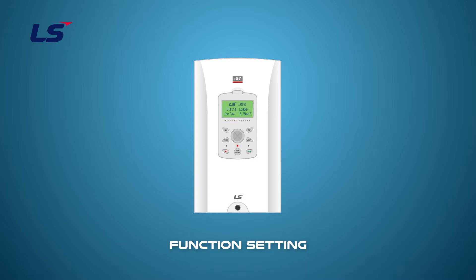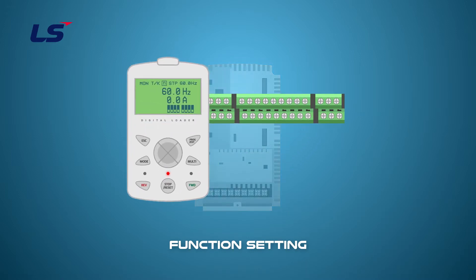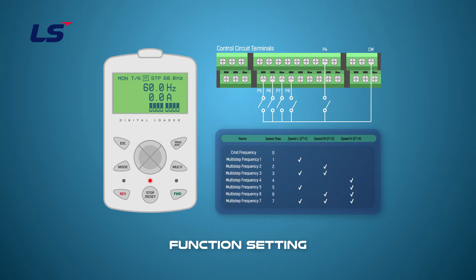The settings for multi-function terminals Speed-L, M, and H operate by binary sequences. The following table shows the input sequence for each single digit. You can also check it on the keypad display. When terminal P5 for multi-step frequency, which is Speed-L, is ON, it is step frequency 1. When terminal P6, which is Speed-M, is ON, this is step frequency 2. The control is determined by the input combinations of the terminals. Additionally, to implement step frequencies 3, 5, 6, and 7, turn on the combinations of terminals P5, P6, and P7.